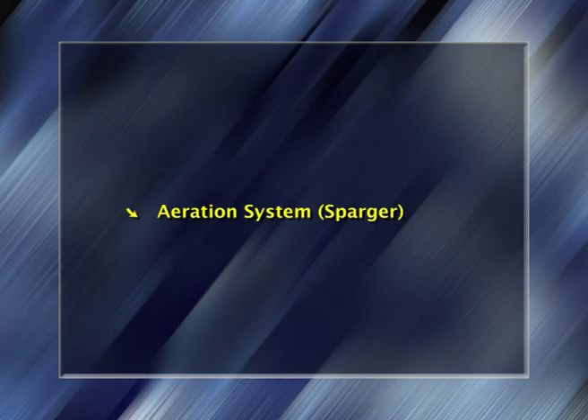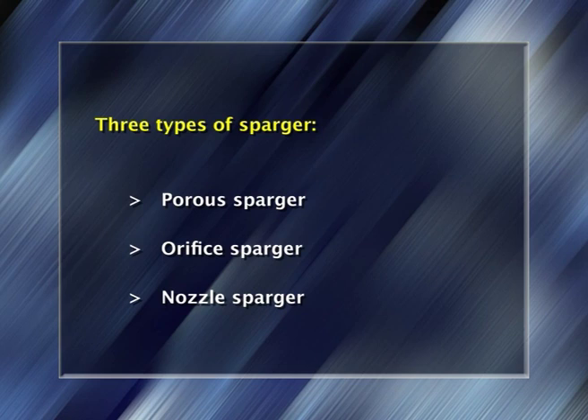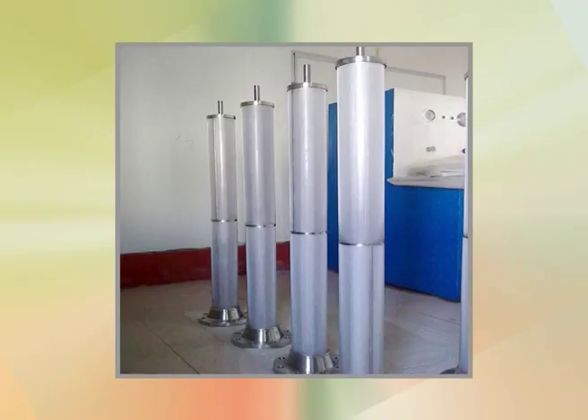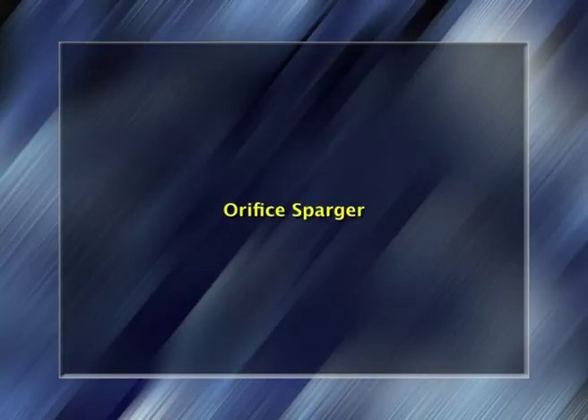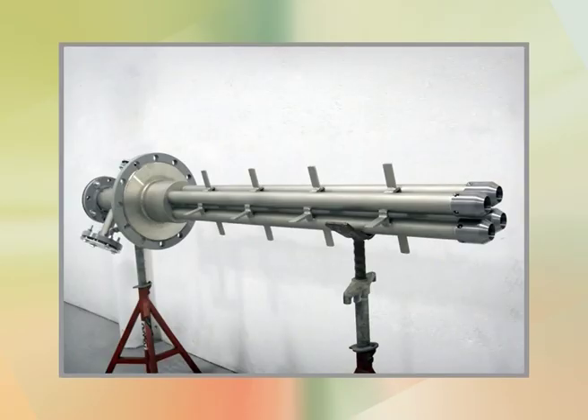The aeration system, or sparger, is a device for introducing air into the fermenter. There are three types of sparger: porous sparger, orifice sparger, and nozzle sparger. 1. Porous sparger: made of sintered glass, ceramics or metal — used only in lab scale, non-agitated vessels. 2. Orifice sparger: used in small stirred fermenters — it is a perforated pipe kept below the impeller in the form of crosses or rings. 3. Nozzle sparger: mostly used in large scale — it is a single open or partially closed pipe positioned centrally below the impeller; when air is passed through, there is lower pressure loss and it does not get blocked.